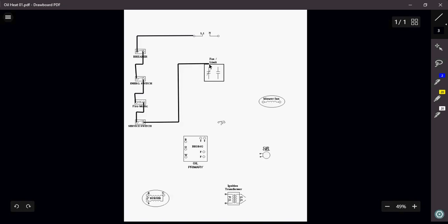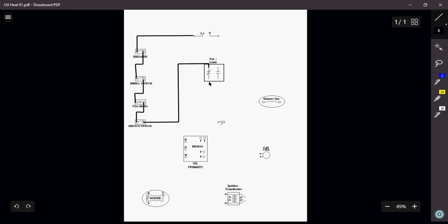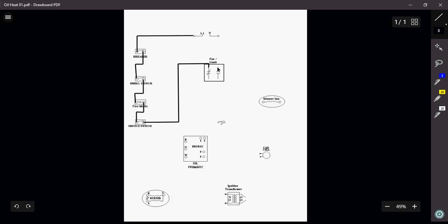The fan limit switch is acting as a safety and a control device. You'll see here that you have a normally closed and a normally open set of contacts. These are temperature-actuated switches. This switch is going to open if the furnace gets up to about 200 degrees. This switch is going to close once the furnace gets up to about maybe 140, maybe 150 degrees. So, this guy over here is actually a safety. This guy is actually going to be used to control our blower fan and turn it on once the furnace reaches a certain temperature.